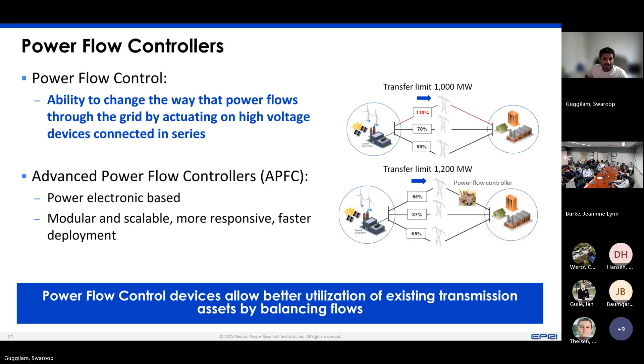Going one level deeper, APFC is essentially a FACTS device—flexible AC transmission system device. Within that category it's called a static synchronous series compensator, or SSSC. You'll hear the term 'modular SSSC' a lot if you search for APFC. All it does is inject a series voltage on the line, perpendicular to the line current.